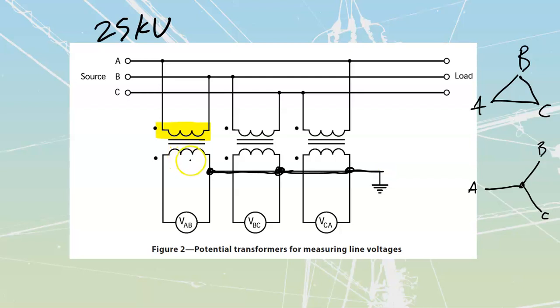Now, if I take a look at my transformers, whatever I have on my A phase over here, my high, I'm going across from A to B. I'm now going to see that as a phase over here on my secondary side. So my voltages that I'm measuring are A to B. It says A to B over here, but it's actually going to be A to N that we are measuring over here. And if we really wanted to measure the actual voltage that we had line to line going across, we would actually have to connect these PTs into a delta type of configuration where I would go from my A over to the B, etc. I'm just going to draw that over top to show you a true line-to-line measurement.